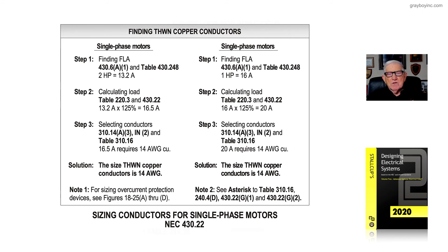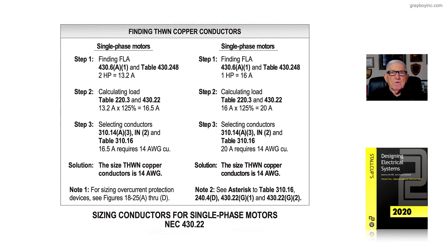That's basically how we size the conductors at 125% of the full-load current of the motor. We've reviewed how to select that full-load current — not the nameplate on the motor.